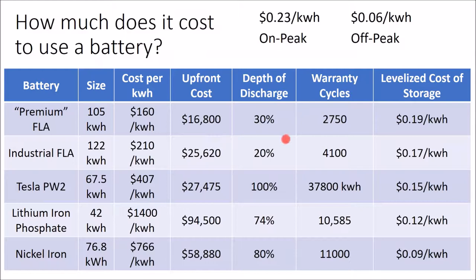You take the number of kilowatt hours you're going to use, and the cost per kilowatt hour to get your upfront cost, then you look at how much of the battery bank on a day-to-day basis you're actually going to use. So if I'm using 30% of a 105 kilowatt hour battery, or 20% of a 122 kilowatt hour battery - how did I come up with 105 versus 122? Well, that's based off the product range of the specific battery you're looking at. Generally you go all the way up to 48 volts for your battery inverter and then see where you end up.